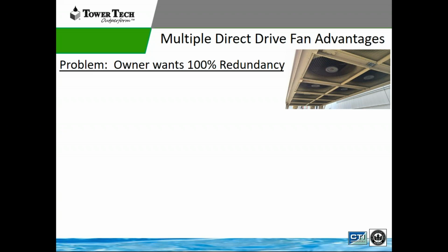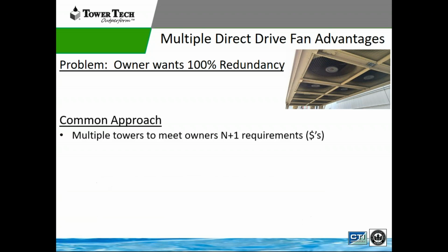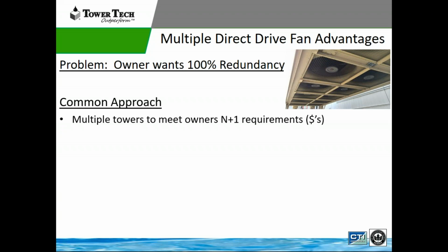Okay, this is a big one. Typically owners want redundancy in their system. On a traditional system, you have a cooling tower that's attached to a chiller. If that cooling tower fan fails, typically that chiller cannot operate. If that chiller cannot operate and that system goes down, then I better have some sort of redundancy if it's a critical chiller. So a common approach for the conventional system is just putting in another tower. If that one fails, then we go to another one.